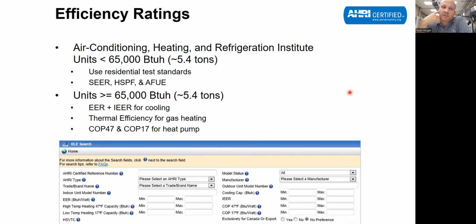And from our perspective, the unfortunate part is none of those tests line up with my life. My life is this building, or it's that building, or it's this house, or whatever it is. And now I got to use this test data. It is what it is, right? So these numbers don't do a great job of telling me what's going to happen in my building. What they do a great job is telling me if I have 2 pieces of equipment that are the same type of equipment from manufacturer A and manufacturer B, how efficient is each one compared to each other, right? They do not do a good job of me comparing disparate types of systems.